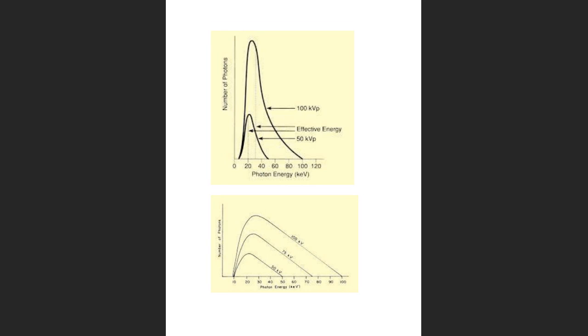And this last one I thought was pretty demonstrative of the different photon energies again. Everything started at 0. Here's your 50 kVp, obviously showing lower amplitude and the lowest quality, because the quality side cuts off at 50 kVp. And then at 75, again, an increase in amplitude, a shift to the right, and an increase in quality.